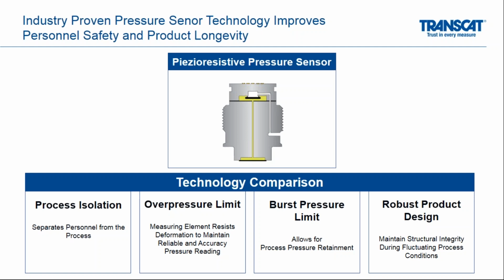One thing that's nice about this is you do have process isolation. The process isn't going into the gauge, and in fact, there's also a separate isolator that can stop any process or hazardous material from escaping. You also get higher overpressure limits because it's not relying on any sort of mechanical piece like a Bourdon tube bending. You can reach a lot higher pressures before any sort of damage to this gauge might take place. And then along with that, from a burst pressure standpoint, it takes a lot more pressure for this kind of gauge to burst, for all of a sudden there to be a catastrophic failure. And ultimately, just a robust design. This has great structural integrity, and it's one of the reasons why we can reach these overpressure and burst pressure limits.